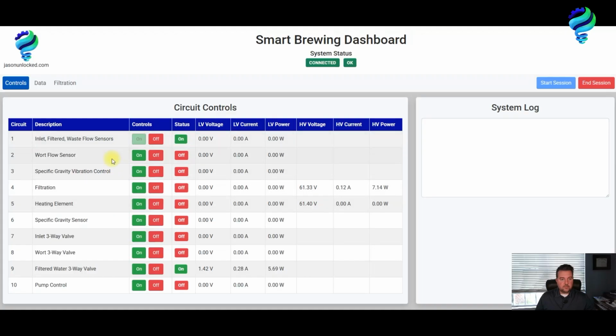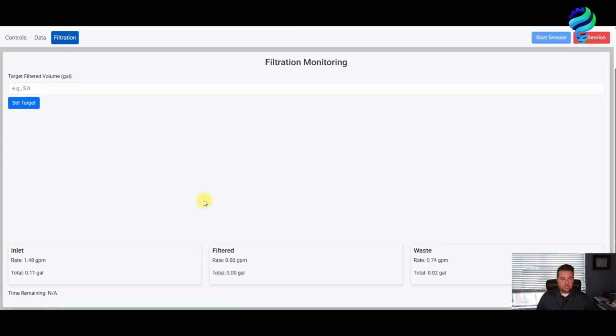Okay, next we're going to turn on the sensors to make sure that we can record data. You can see 5 volts on those. That's good. Now we're going to turn on the filtration system. The filtration system won't work until it's receiving water. It has its own pressure transducers built into it, so it can automatically detect and turn itself on and off. So turning it on is safe. It does nothing, and it's not going to burn out the pump or anything. You can see we're reading as expected there. And then finally we're going to turn on the on-off valve to give it water. Okay, so now the system is on.